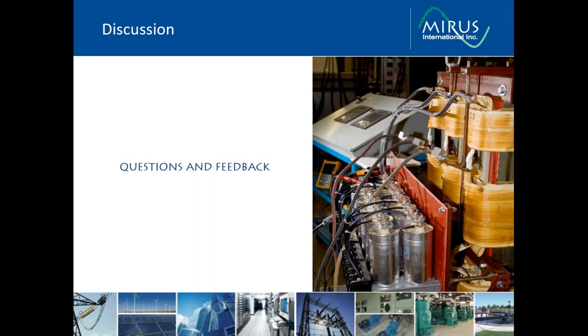The next question is, can you provide a functional description of a wide spectrum harmonic filter? In other words, what is a passive harmonic filter consisting of? Sure, so the wide spectrum harmonic filter has basically three main components. There's a main blocking reactor on the input that's a series connected reactor. There's a parallel tuned branch, so there's a reactor component in the tuned branch, and that's where the capacitors are connected. And then there's a compensating reactor on the output to improve performance and reduce the voltage drop across the filter. So that's a typical configuration.